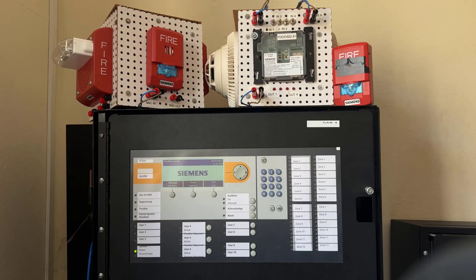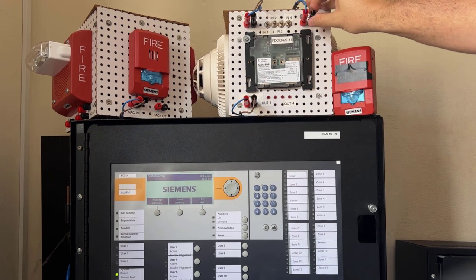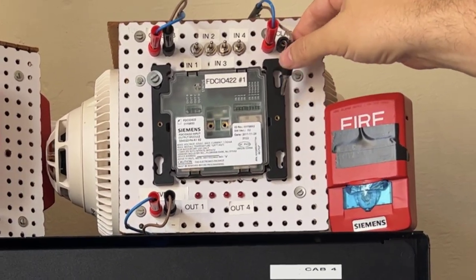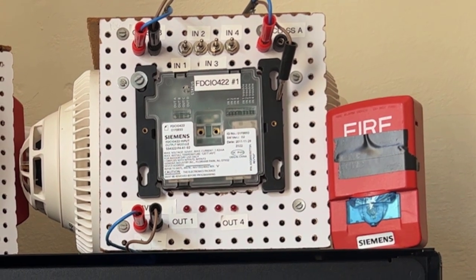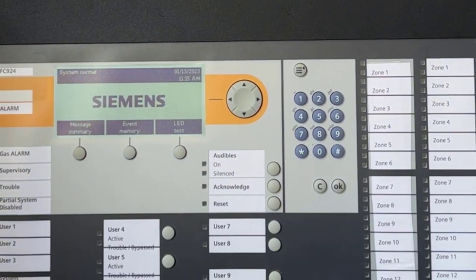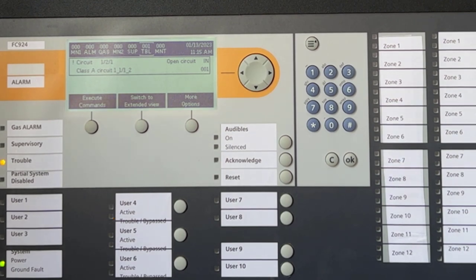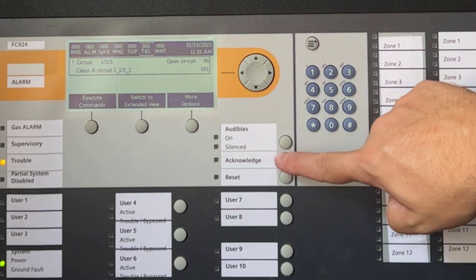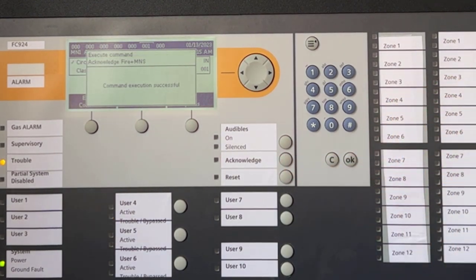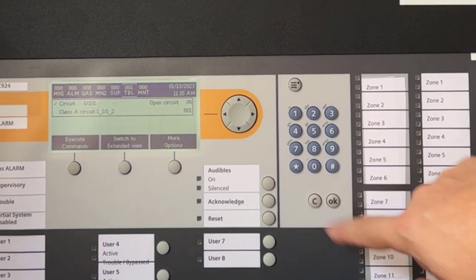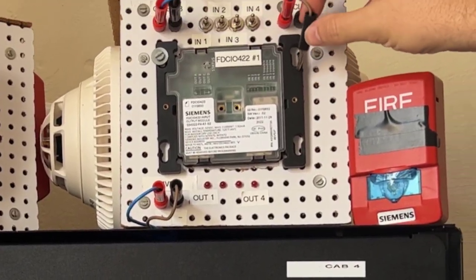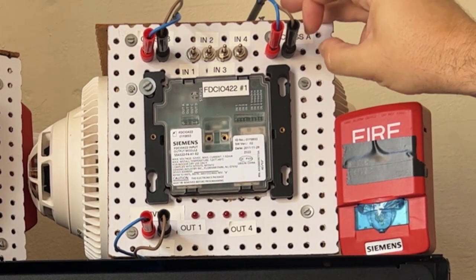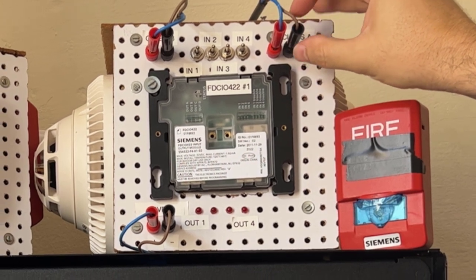Our first problem case is an open loop in a Class A configuration. First, you can see a trouble-free system and I will induce an open-circuit trouble. You can see the trouble coming in, as expected, and upon fixing the issue the panel self-restores to its normal condition.